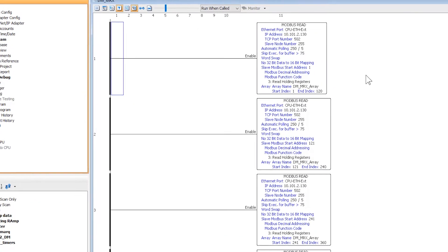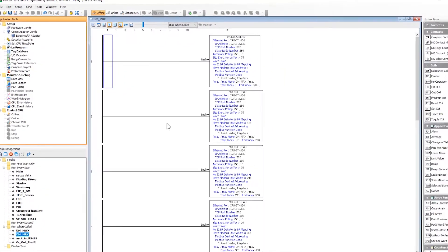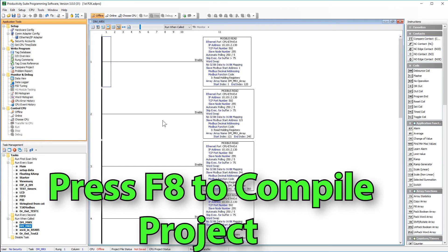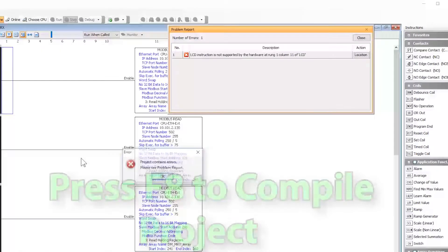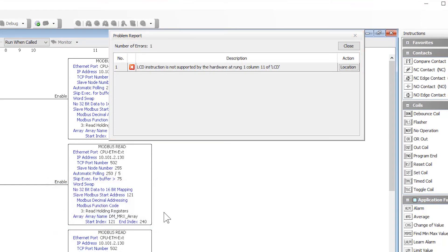Now if I go in and look at my ladder code, I can see that all of my tasks converted over. One final check: let's compile our project to verify. Press F8 and I got an error message. Looks like I was using an LCD instruction. And since my P1000 does not have a display on the CPU, this instruction will not work.